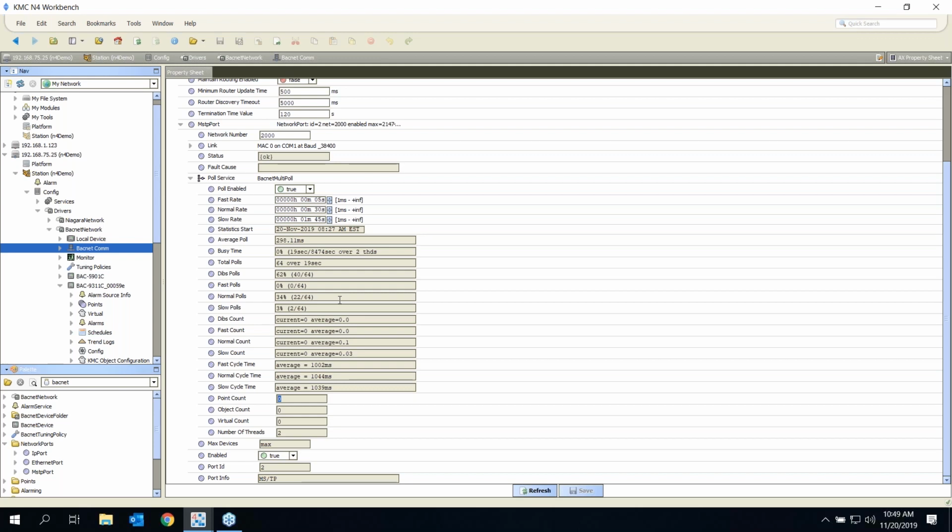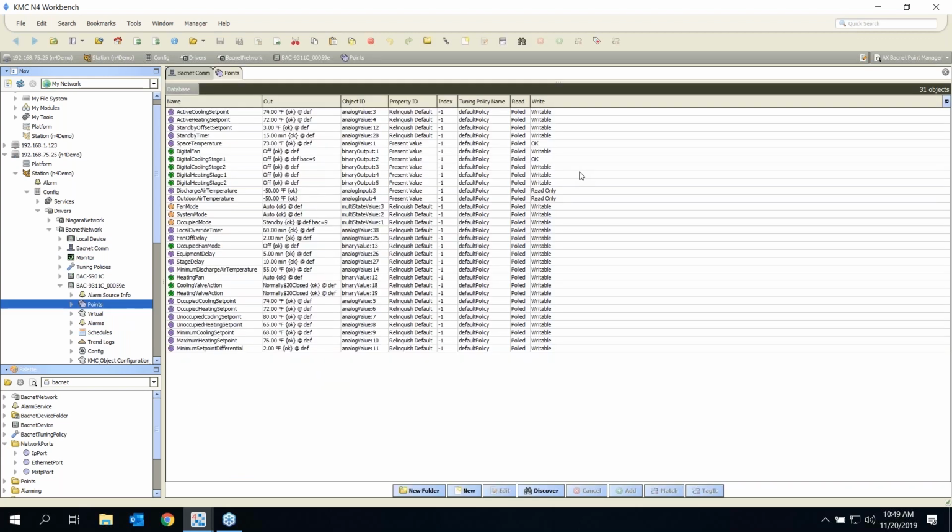So when the driver wants to poll something is when there's an active interest in that data in the station, and that's what we call a subscribed point in Niagara. And things get subscribed by looking at them, like in a point manager or PX view, wire sheet, or things like that, and those cause transient subscription. And then permanent subscription is caused by having things like history extensions and alarm extensions and control logic and that sort of thing.